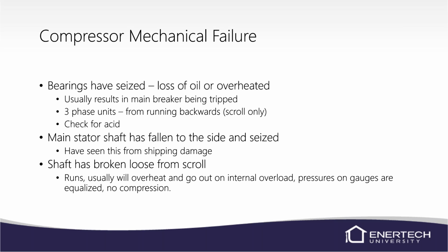If you do have a bearing seize and you're tripping the breaker or you're shorted to ground, always check for acid in the system. Again, we have those Checkmates. Most supply houses have them. They're single use. After you've checked it, you can send it in with the warranty analysis form. And if we ask for the compressor back, send it in with it. Tape it to the side of the compressor. That way, if we need it, we have it.